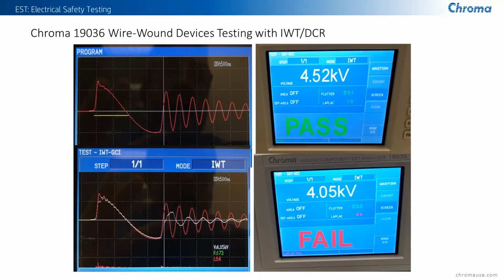And then down below, on a failed part, you'll see that it starts to show that partial breakdown, which would be the differential, which would be the partial discharge occurring. It would also show up in what we refer to as the differential area as well. Those are indicated below by the voltage at a lower voltage, and the levels that we've detected for a fault on Laplace and flutter as well. And so from there, you can clearly indicate if it's a pass or a failed condition.